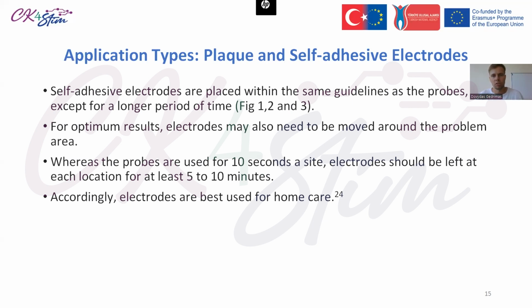Another type of application is self-adhesive electrodes. They are placed within the same guidelines as the probe, around the painful areas, except for a longer period of time. If we place an electrode there, we leave it for a certain time, for example 5 to 10 minutes on this spot, and we treat it with microcurrent stimulation. For optimum results, electrodes may also need to be moved around the problem area. This is a little bit uncomfortable compared to probe electrodes.